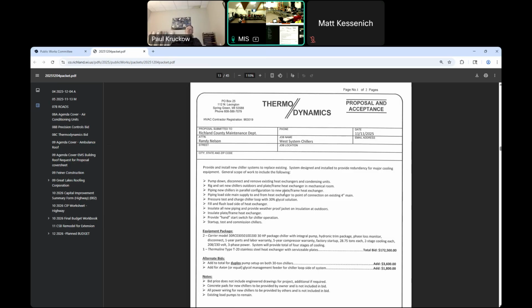Certainly would be worth exploring that, so that you either replace them now and we do all the pumps, and if they're the same body, you take the old pumps and rebuild them maybe, that sort of thing, or you put them in and have a backup pump. They're all 3 the same, and we have a 4th one that's our backup. So that if any one of these individual zones goes down, you have the ability to get it up and running within a reasonable amount of time. On my proposal, I gave you 2 alternates. One was for dual pumps on the chillers.